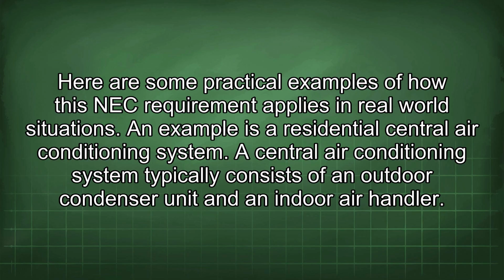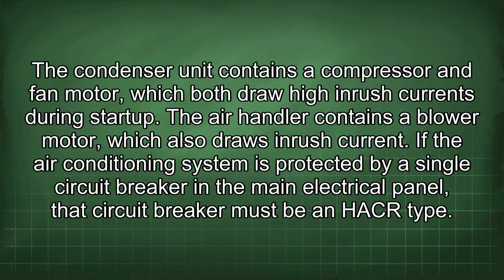An example is a residential central air conditioning system. A central air conditioning system typically consists of an outdoor condenser unit and an indoor air handler. The condenser unit contains a compressor and fan motor, which both draw high inrush currents during startup. The air handler contains a blower motor, which also draws inrush current. If the air conditioning system is protected by a single circuit breaker in the main electrical panel, that circuit breaker must be an HACR type.